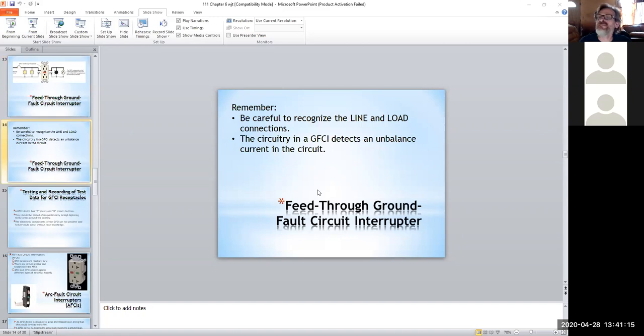Always look in the back—don't assume. It's very clearly labeled; it'll tell you line and load, one portion and the other, and they are broken away. Even the screw terminals on there cannot be matched up unless you actively did it. I'm not sure why, but otherwise it won't operate correctly—it won't be able to detect that imbalance.